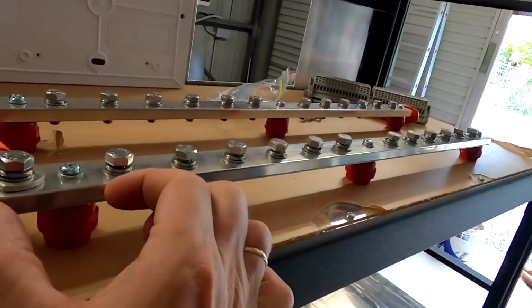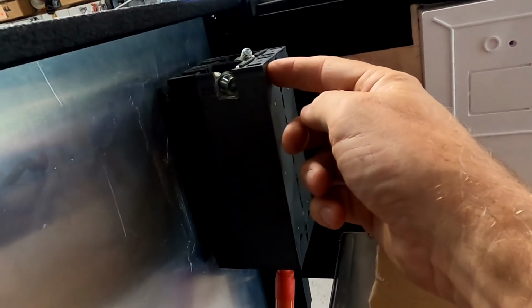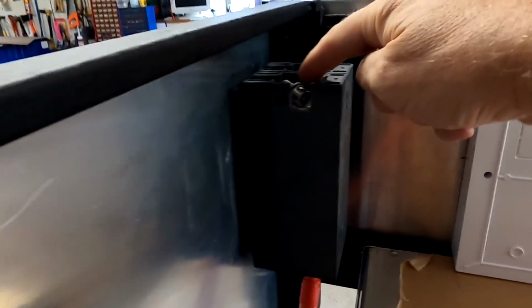We could potentially get something done with a short bus bar link again and mount this from the back side here without using these ones at the front here. Could be a solution, but on the other hand, I don't want to use too many bus bar links and connections for this whole installation, because every link, every connection means more points of failure. So yeah, but it is an option.